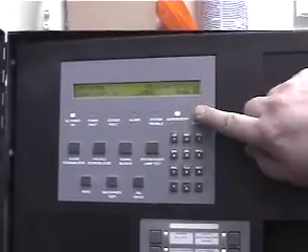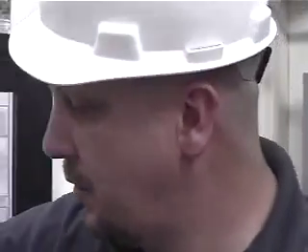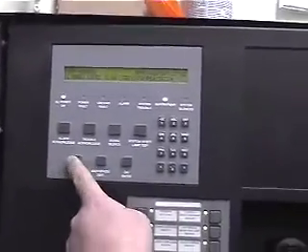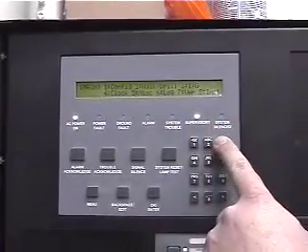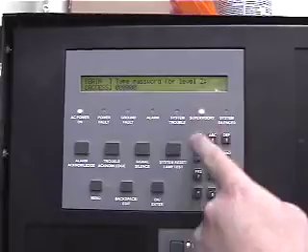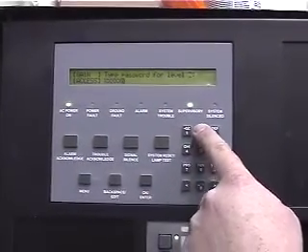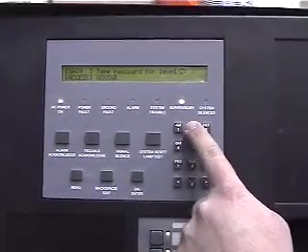So basically, on your remote, it's this module here, the LCD, and anything you can do on this thing, you can do on the remote annunciator. Before we go do an alarm or whatever, we can go through the menu options. You got your menu. If you want to bypass something, 3 for your I/O. Level 2 is your password, 6 2s. Any time it comes up asking for a password, it's just 6 of the number.